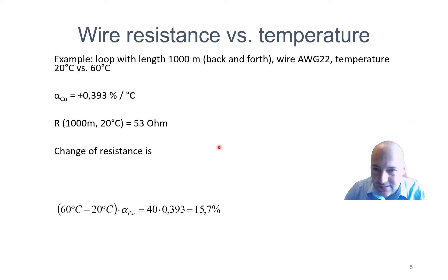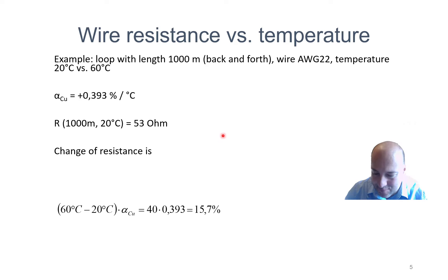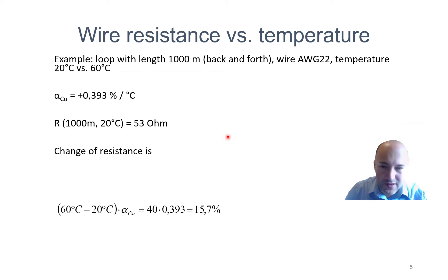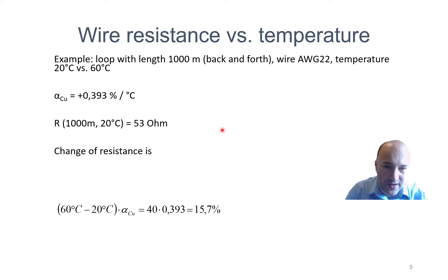Why is it important to know about wire resistance? The current loop and voltage signal will both be influenced by the wire diameter. For the voltage signal, the wire resistance definitely matters. For the current signal, it is only a problem above some limit. The wire resistance changes with temperature, which can be quite significant and may degrade our voltage signals.